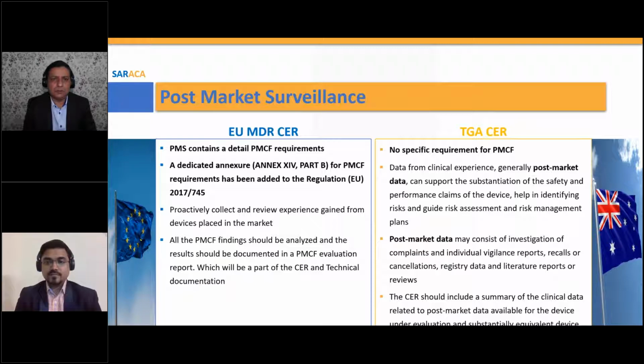A dedicated Annex XIV Part B for PMCF requirements was added to the regulation in the EU in 2017. And this specifically talks about proactively collecting and reviewing experience gained from devices placed on the market.